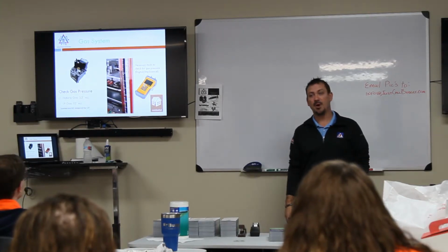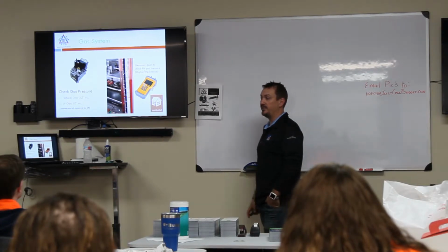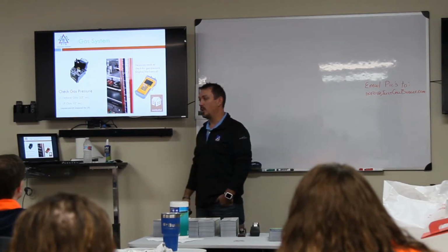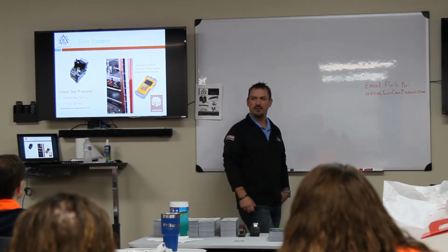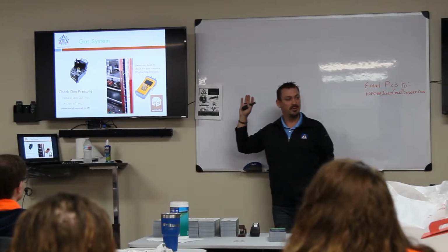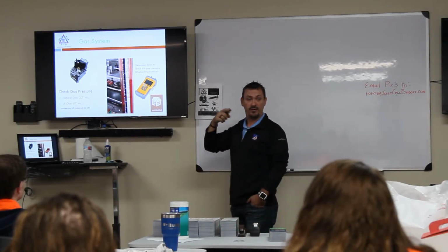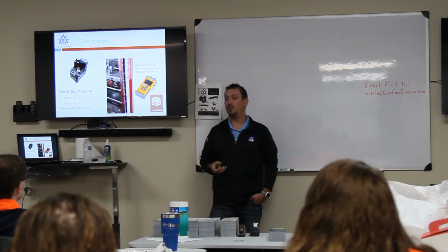Next, we're going to check the gas pressure. This right here is one of the most important things that you can do during a clean and check. This is the thing that you're going to do that is going to mostly affect the efficiency of the equipment. Has anybody in here ever used a combustion analyzer and know what the readings actually mean? Has anybody used a combustion analyzer? You have? Okay. On the combustion analyzer, what it will tell you is the efficiency of the equipment and what it's running at.